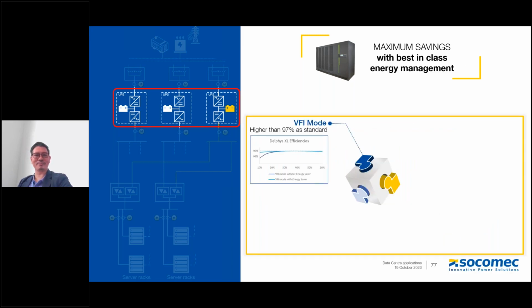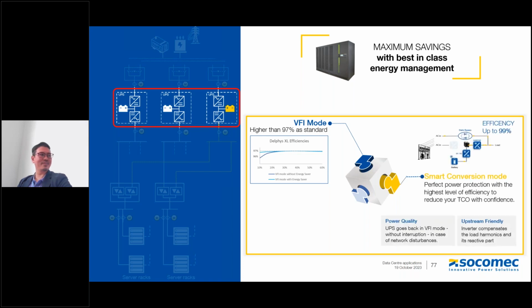We've seen how UPS technology has evolved in the market, particularly how IGBT technology is becoming more efficient. Standard IGBT 3-level technology can now achieve 97% efficiency—that's the current market standard. If you want to go further, there's what we call smart conversion, which basically runs the UPS through the static bypass while maintaining power factor and keeping harmonics at a low level. This interacts with the line to provide good power quality feedback upstream, while ensuring safety—no harmonics, no changes in power factor.